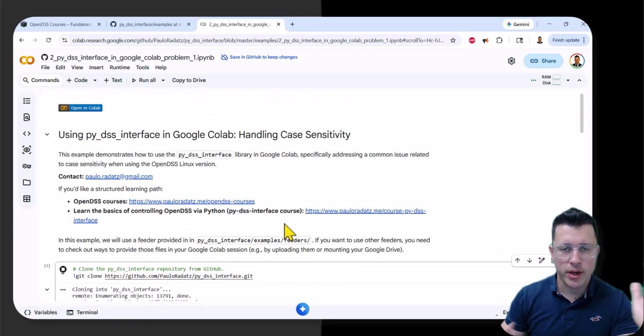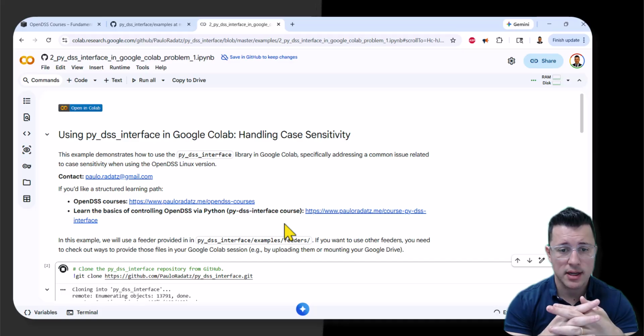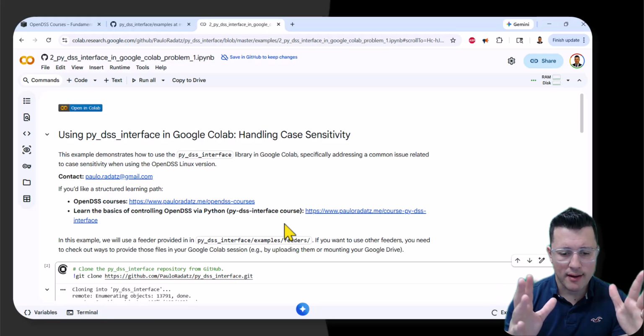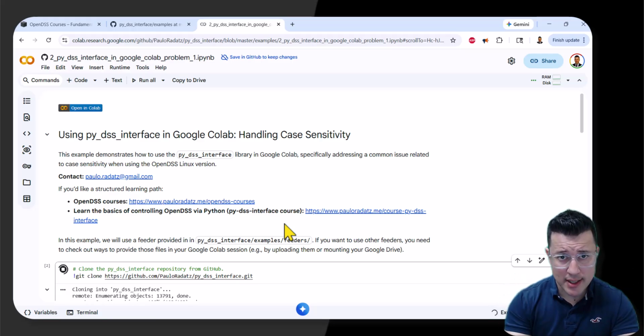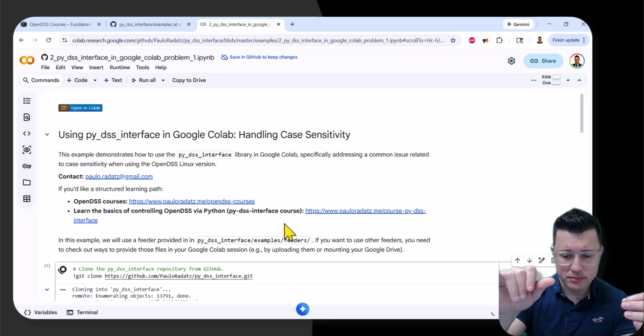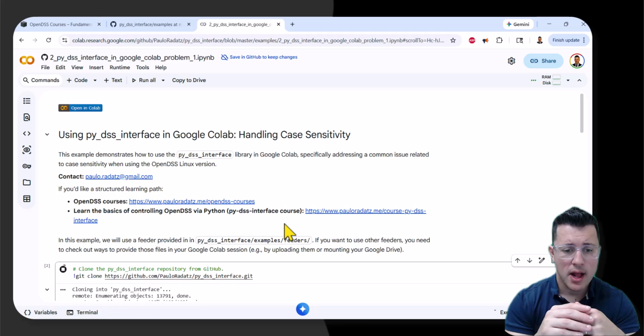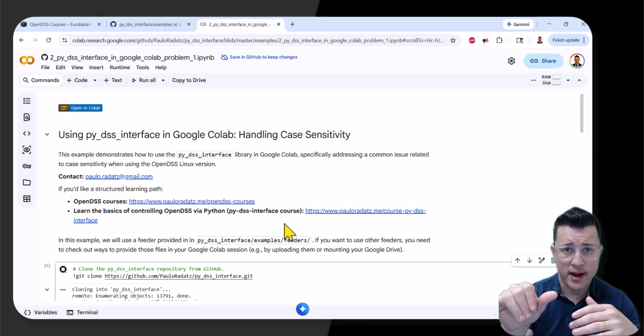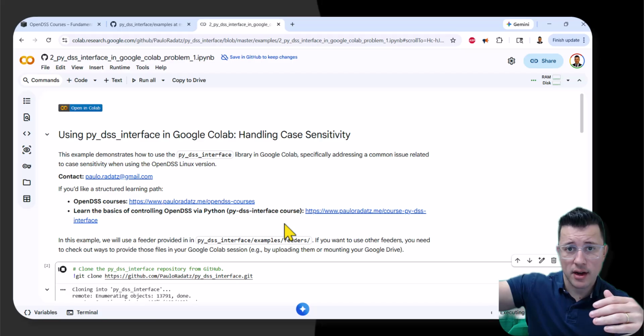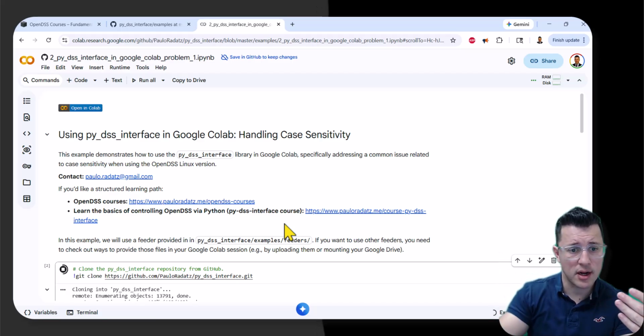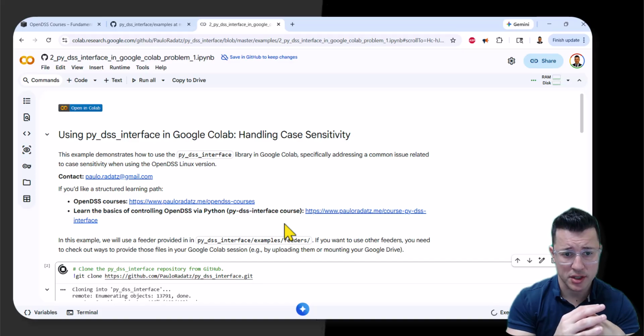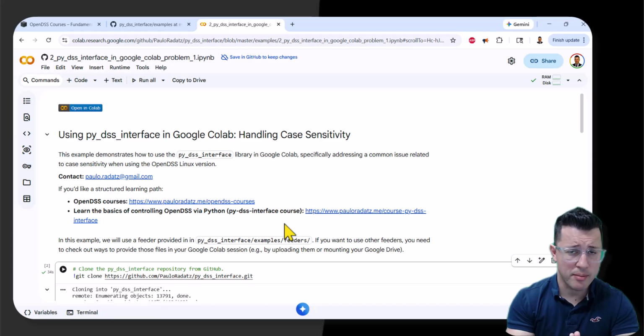One difference between Windows and Linux is that Linux is case sensitive, right? So when we have our models, we have the compile and redirect commands in OpenDSS that we can put the name of the file. If the name of the file doesn't really match what we have in the file, you see an example here, we're gonna have problems in the Linux version. So in the case I'll show you here, it tells me there's a file with a problem, but there are cases when I try to run it, it just says that solution aborted.